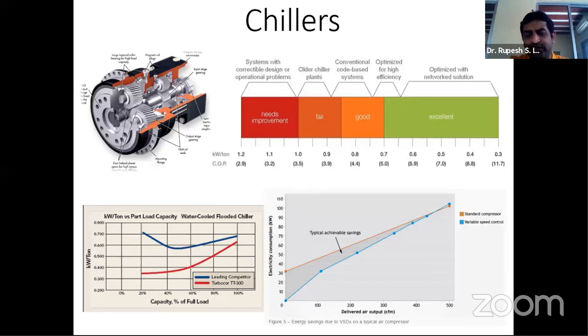Of course, magnetic levitation technology has played a very important and key role in revolutionizing the compressor itself of any chiller plant. And that is what has probably reduced the noise levels, the vibration levels, and at the same time increased the energy efficiency levels. So if you look at, I just took out this graph from one of the manufacturers, and what it says, it gives us the kilowatt per ton in the plant, in the part load, the capacity of a water cooled chiller.